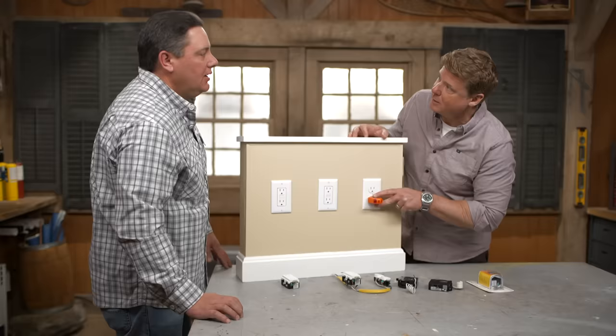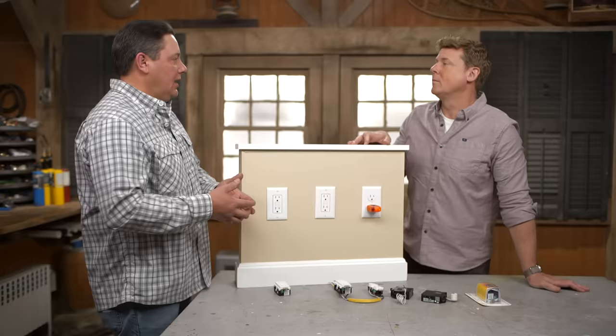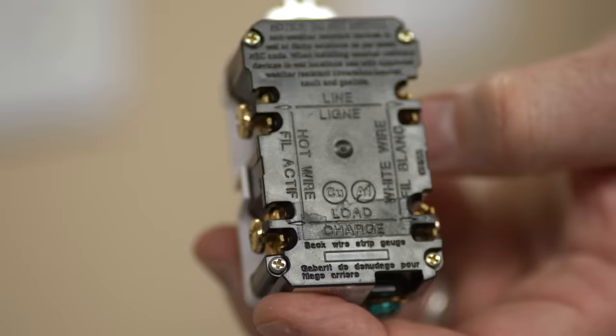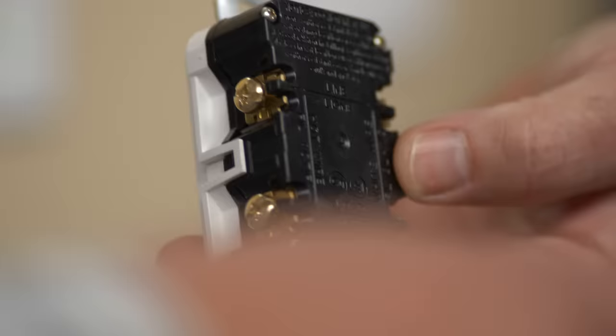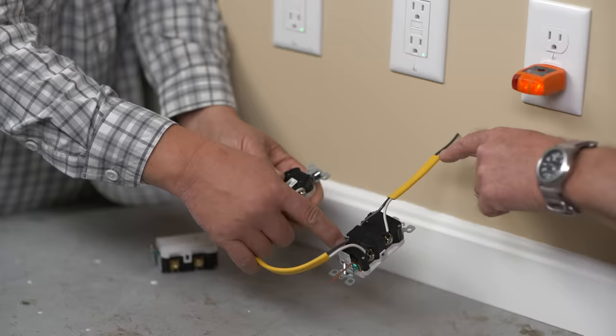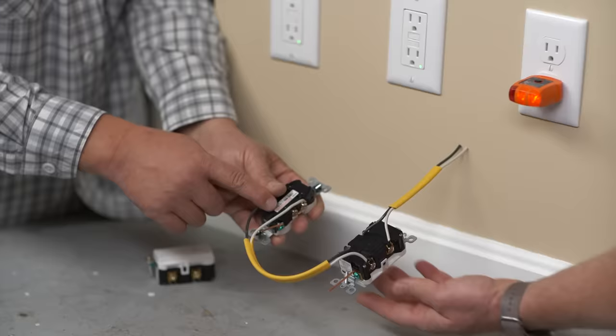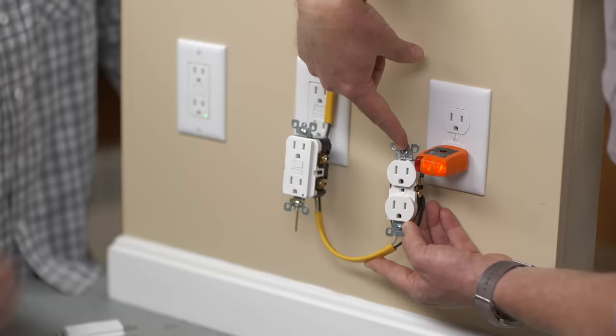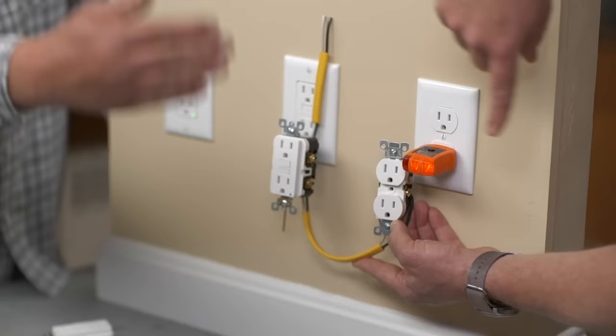It was very common that if you had, let's say, three bathrooms in the house, the very first bathroom closest to the panel — they'd run the power from the panel to put the GFCI there. Then from this point, they'd go to the other receptacles. They'd come into what's called the line terminal on the GFCI and then come out on the load. So line is up top and it wants to load down on the bottom. Power coming into the line and back out to other receptacles to the load. So you'd have your line conductor there and your load conductor down to there. This is the line coming in — you've hooked it up to the place that says line. And then this is the load coming out, and that goes to the next receptacle. Basically it's doing the exact same thing — I know that's protected. Because it's tied to this, this is protected as well. And you can keep going down, and those are all protected from that point forward.